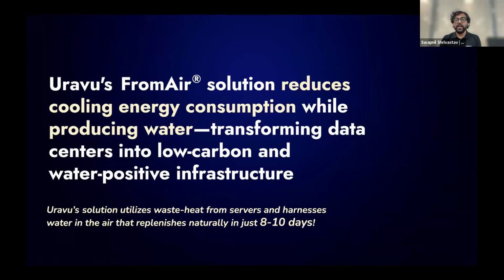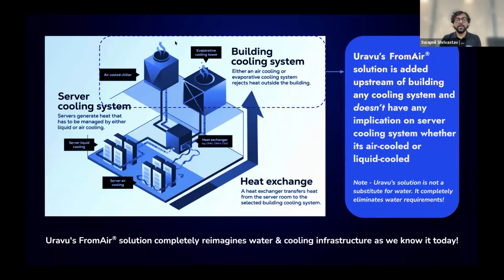So we are designing a very flexible software and hardware platform which, depending on your waste heat load, which is basically all IT load converted to waste heat, utilizes that to reduce cooling energy consumption while also producing water from air in the process. So the idea is data centers can convert to a low carbon and water positive infrastructure rather than being water guzzlers and emitting carbon emissions. That's the whole idea of what Uravu does. And we don't interfere anywhere at the server level. Whatever hot water gets carried through the facility water to the outside of the data center hall, mainly to a cooling tower or chiller, we will intervene there and reduce both the cooling and water side of the equation.